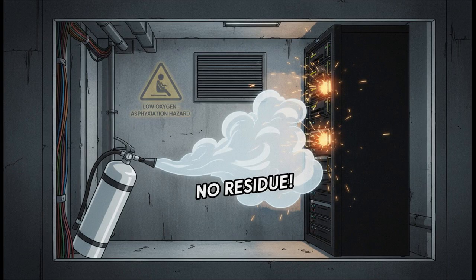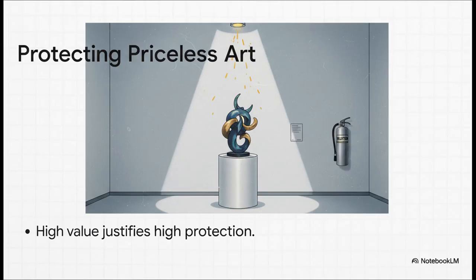In a small, unventilated room like a server closet, they can actually displace so much oxygen that they become a real asphyxiation risk to the user. Now, for the places where you have truly irreplaceable stuff, we're talking data centers, museums with priceless art, or critical hospital control rooms, you're going to specify a clean agent like Halotron. It's clean, it's safe for electronics, and it's much safer for people than CO2. The only real downside? The price tag. But when you're protecting mission-critical assets, that cost is pretty easy to justify.